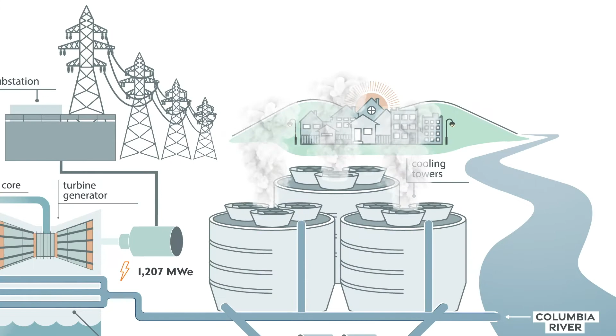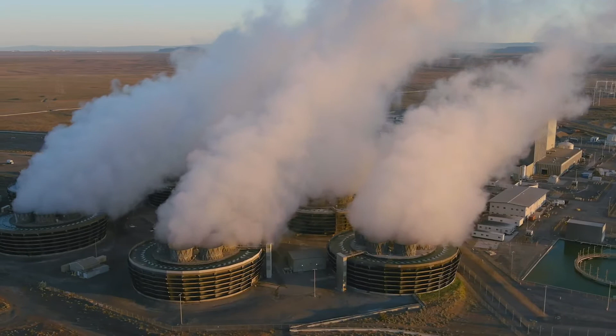Columbia operates on a closed-loop cooling system, drawing about 22 million gallons of water daily. To put that into perspective, about 35 to 50 million gallons of water flow past the intake structure every minute. The water inside the condenser pipes absorbs a lot of heat, so to cool it, we have 6 mechanical draft cooling towers.